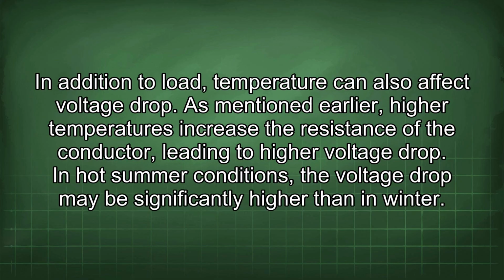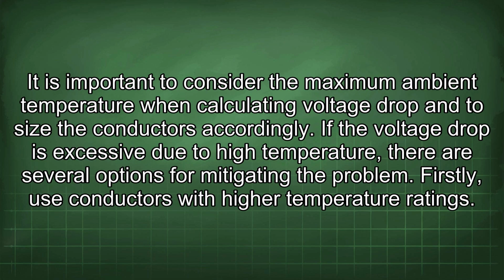In addition to load, temperature can also affect voltage drop. As mentioned earlier, higher temperatures increase the resistance of the conductor, leading to higher voltage drop. In hot summer conditions, the voltage drop may be significantly higher than in winter. It is important to consider the maximum ambient temperature when calculating voltage drop and to size the conductors accordingly. If the voltage drop is excessive due to high temperature, there are several options for mitigating the problem.